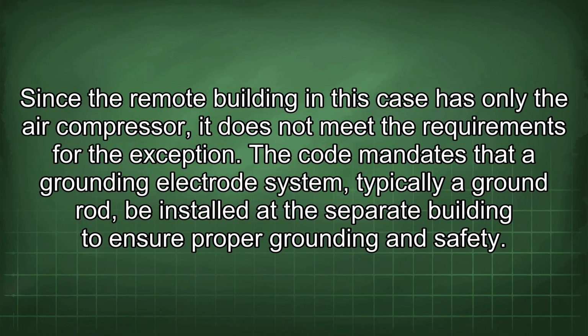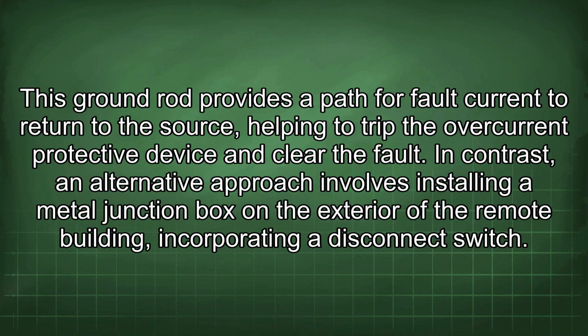Since the remote building in this case has only the air compressor, it does not meet the requirements for the exception. The code mandates that a grounding electrode system, typically a ground rod, be installed at the separate building to ensure proper grounding and safety. This ground rod provides a path for fault current to return to the source, helping to trip the overcurrent protective device and clear the faults.